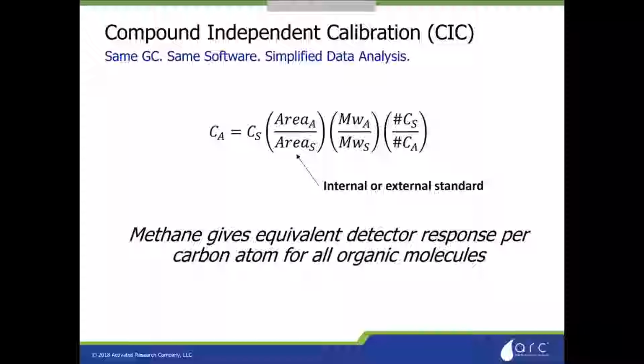It's important to note that anytime you do a calibration, you're actually introducing error into your system, whether that calibration standard was mishandled or made improperly, there is a risk there. And then when you open that and handle it yourself, put it into a syringe, you can lose analytes that way. We have customers who break open calibration standards and half of their molecules boil off because it's a mixture of low and high volatility compounds. So by doing this and circumventing the issue of calibration, you can actually increase your accuracy. And with calibration, you would not know, you would propagate those errors throughout the analysis.